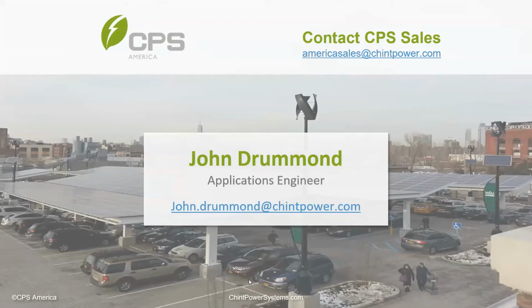What is the smallest size inverter the FlexOM unit can be installed if a customer wants to retrofit their sites? Currently the FlexOM is compatible with our 25, 36, 50, 60, 100, and 125 kilowatt design. The FlexOM itself is also compatible with some of our legacy inverters like our 2328 and our 14 and 20. However, those models are not supported on the FlexOM portal. So to clarify and answer the question, the 25 kilowatt 480 volt string inverter that we currently have is the smallest inverter the FlexOM can be installed on.